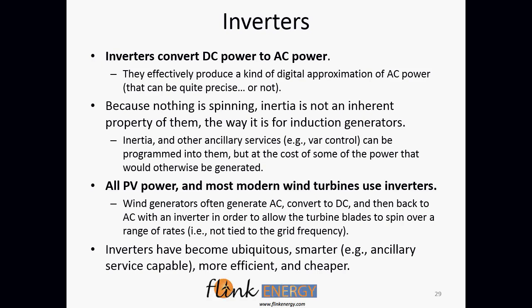They had the same problem the other way, which is really worse. The inverters are programmed to protect themselves and the grid by coming offline if the frequency drops below a certain level. They had an outage of a major power plant, and the frequency dropped, just as we saw, slowing down when you spin this thing, when they lost a generator, because all the other generators were trying to meet the load without it. The frequency dropped, and then all the solar on the island dropped out at the same time, and because that dropped, it just made the situation worse. They almost lost everything and went to a blackout. So they're very concerned about that.